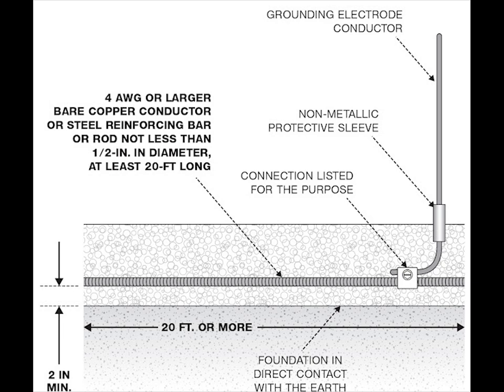The code refers to Ufer grounds as concrete encased electrode. The code requires that the concrete encased electrode must be encased by at least 2 inches of concrete and located within a portion of concrete foundation or footing that is in direct contact with the earth. You must route the grounding electrode conductor into the footing and connect it to 1 or more bare or zinc galvanized or other electrically conductive coated steel reinforcing bars or rods of not less than ½ inch in diameter, installed in one continuous 20-foot length, or if in multiple pieces connected together by the usual steel wires, exothermic welding, or other effective means to create a 20-foot or greater length. And the URL is listed below.